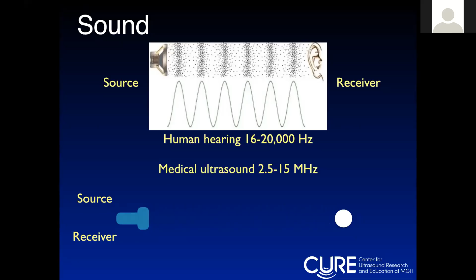How does sound work? Generally, there's a source, such as this little speaker, and then there's a receiver. The sound wave goes and hits, and when the sound hits, the receiver hears it, and that's called hearing. Human hearing is up to, the frequency is up to 20,000 hertz. Medical ultrasound is 1,000 times higher frequency than that. And so here's your probe, and the probe acts as the source. It sends out a signal, and that signal travels, and then it hits an object. It bounces off the object, comes back to the probe, and the probe is also the receiver.